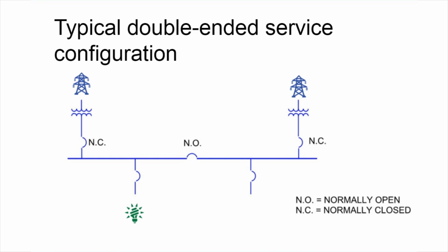It's really important when you're looking at this type of configuration to understand how to size your buses. You need to make sure that when the bus is closed and we're carrying all the loads from one side, there's enough capacity. If not, you're going to have to look at how you shed load when you go to a single source. That could be done with a Kirk key interlock if you put a manual tie breaker instead of an automatic tie breaker in between the two buses.